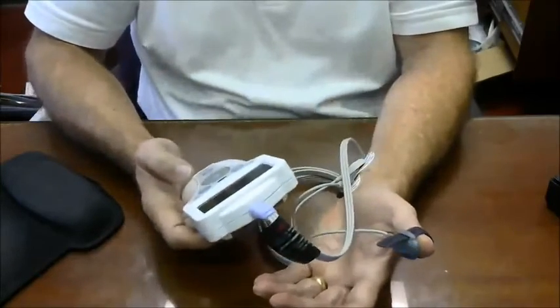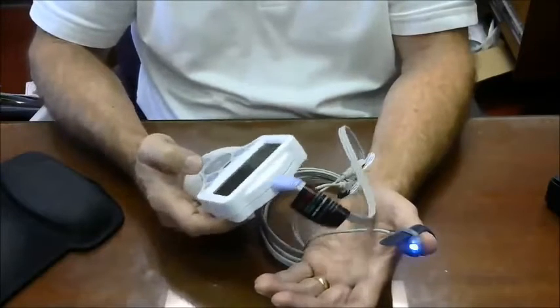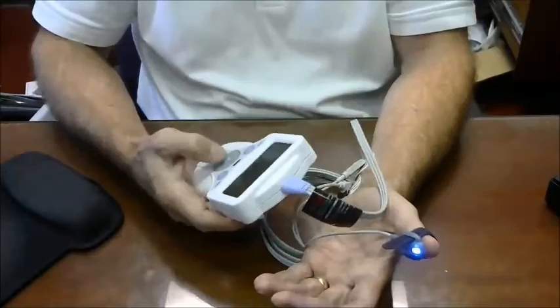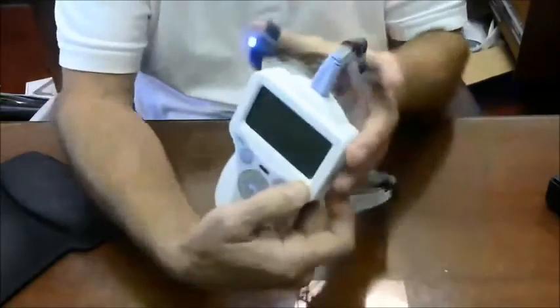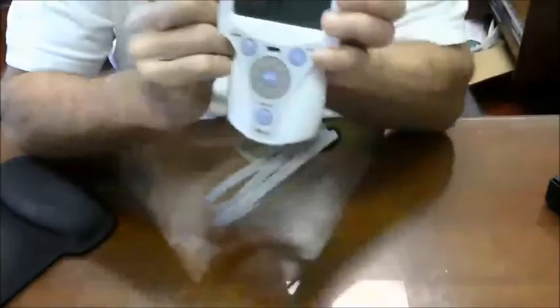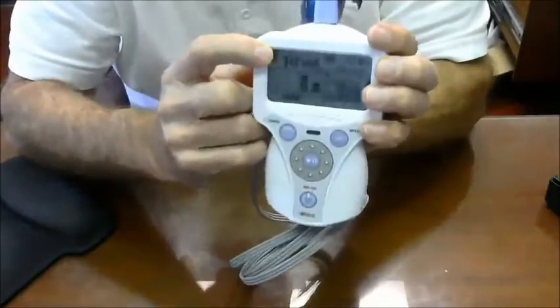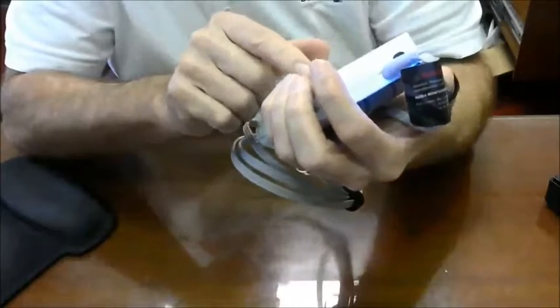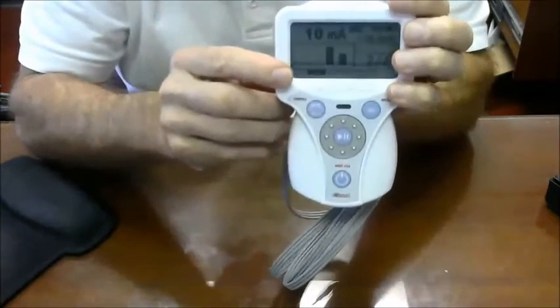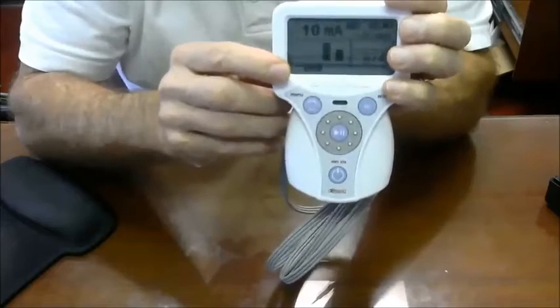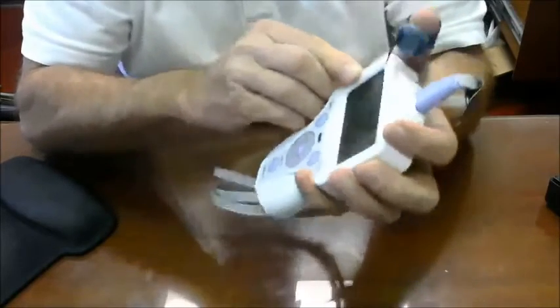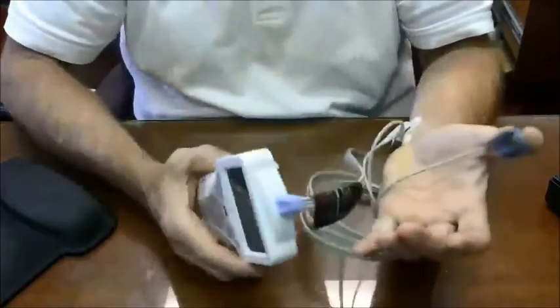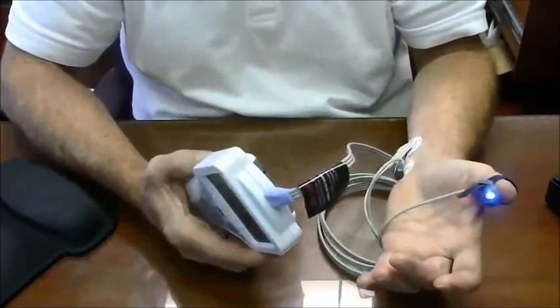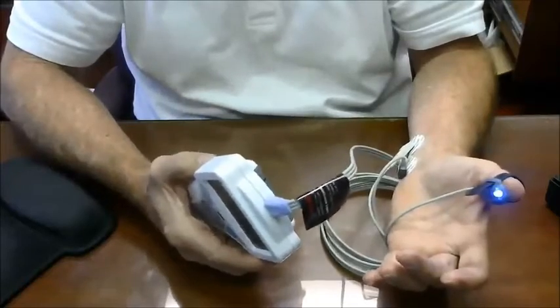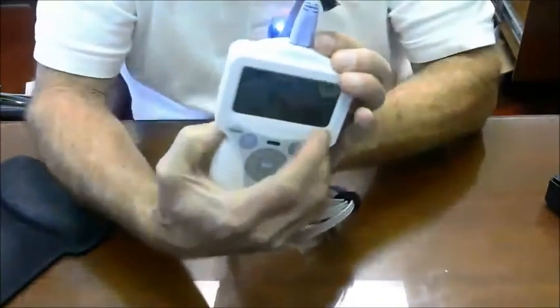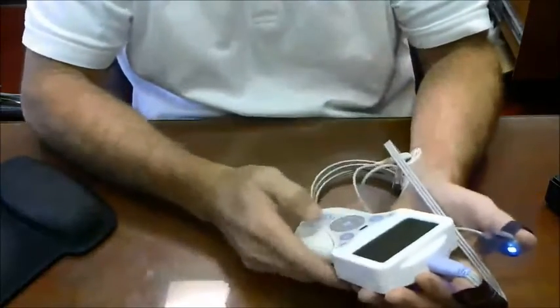If I wanted to show a patient that was having fade, in other words, they're coming back just off of anesthesia, there are some things I might point out on the display. First of all, there's a thing that says what milliamps we have set, and then there's a reading next to this that says 10.0 milliamps approximately. So that's telling you what was delivered. So with this device, you always know what you have it set at and what was actually delivered. So if you do a stimulation and you get 0 of 4, and they're concerned that maybe a stimulation wasn't actually given, they would then look at the display to see, yes, 10 milliamps was actually given.